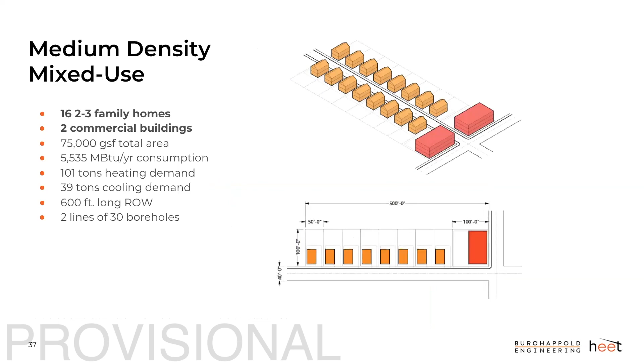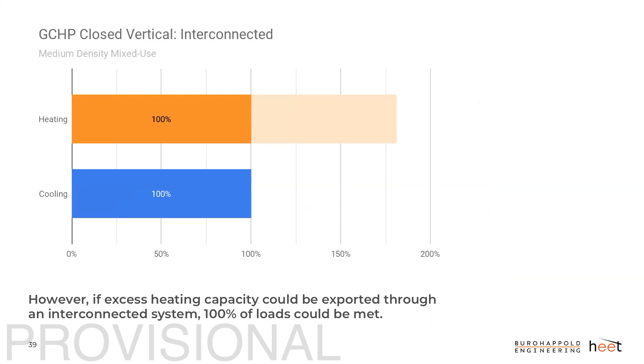For the medium density mixed use, this was our best candidate because you had a fair diversity of loads, with some retail commercial uses providing cooling that could balance out the heating. Under the balanced condition, where we don't want to address thermal degradation and want to be safe, you can meet 100% of heating loads and about 60% of cooling loads. If you open it up and interconnect, you can meet 100% of both loads, but you would need to export that heating energy elsewhere to maintain thermal balance, at least for those boreholes.